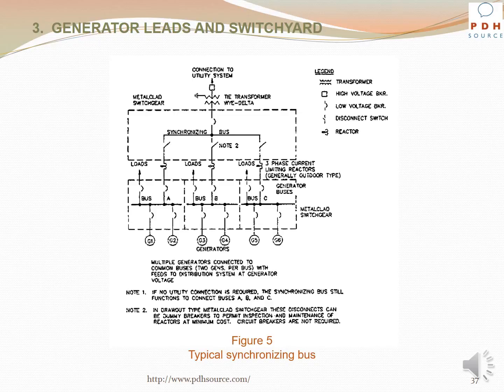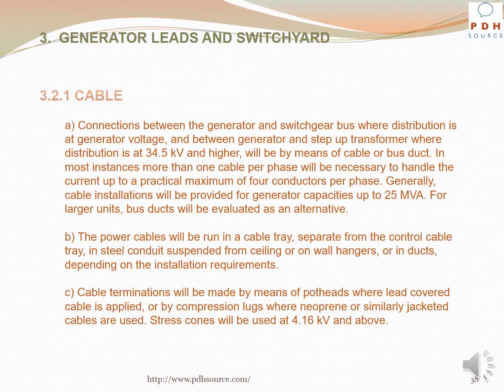Figure 5 indicates typical synchronizing bus arrangement. Connections between the generator and switchgear bus where distribution is at generator voltage, and between generator and step-up transformer where distribution is at 34.5 kV and higher, will be by means of cable or bus duct. In most instances, more than one cable per phase will be necessary to handle the current up to a practical maximum of 4 conductors per phase. Generally, cable installations will be provided for generator capacities up to 25 MVA. For larger units, bus ducts will be evaluated as an alternative.